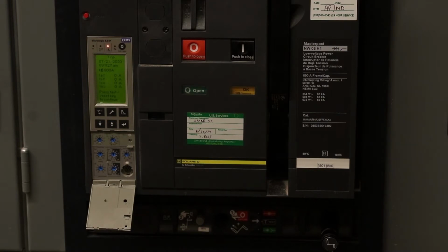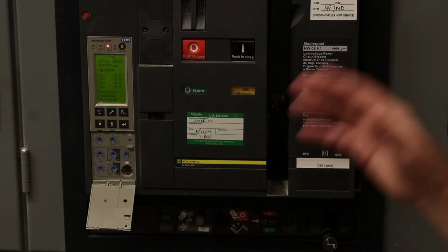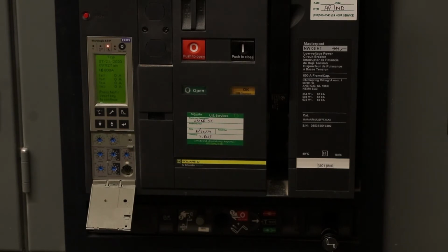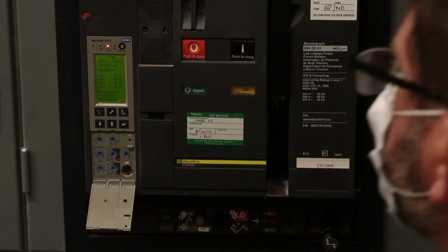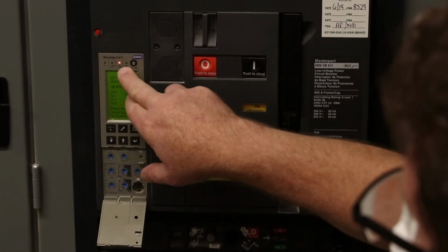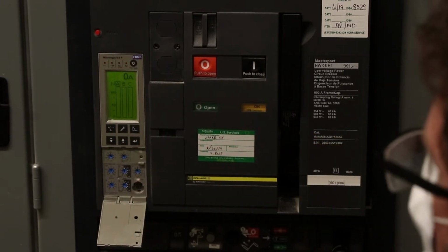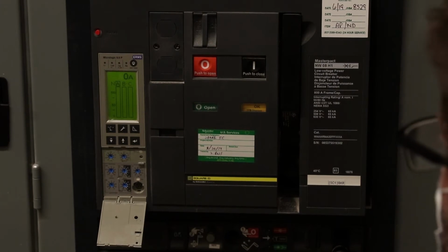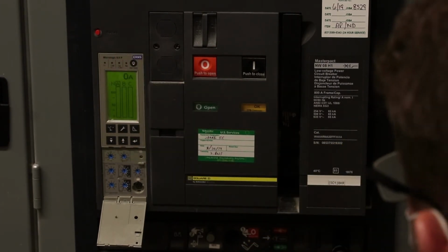We had an issue at, I think it was a Harvard facility years ago, where a breaker tripped for some reason. They just closed the breaker back in immediately. Well, when the breaker tripped, the contractor had left a wrench in the switchgear. And the jumping of the switchgear, or the breaker opening, caused the wrench to fall down on the bus. So when they just closed the breaker back in, it had a real fault. If you have a trip, you want to find and correct the fault before you re-energize it. So you reset that. The other thing, to reset that indicating light, you push the little test reset button. Notice when I push that, that cleared.